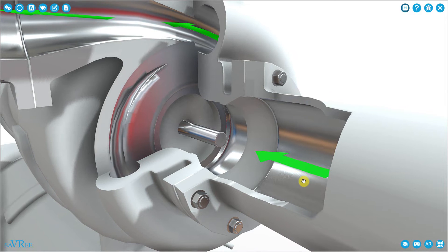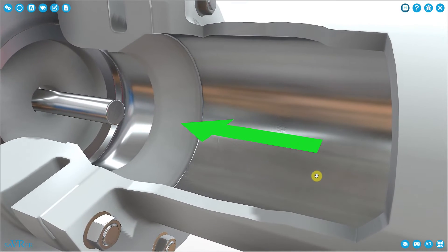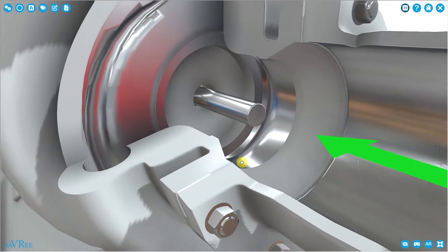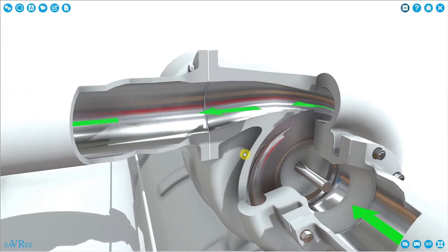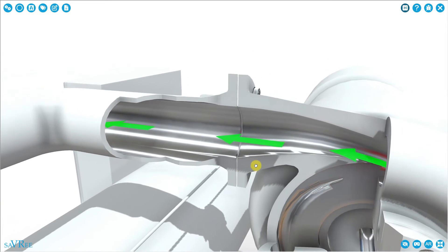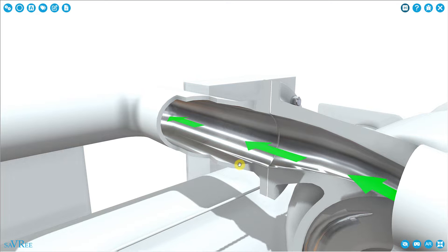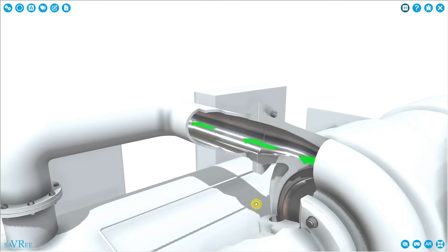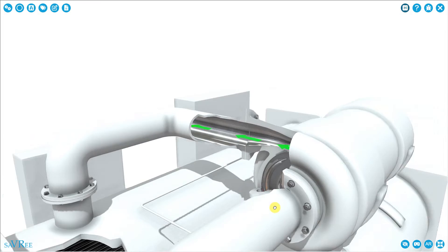We've got a low pressure, relatively low temperature, refrigerant vapor that's been drawn into our compressor. The compressor compresses the refrigerant, which causes the temperature and pressure of the refrigerant to increase, although the refrigerant is still a vapor at this stage. We can use different compressor types to achieve this. The most common being the centrifugal design, the one that we're looking at now.